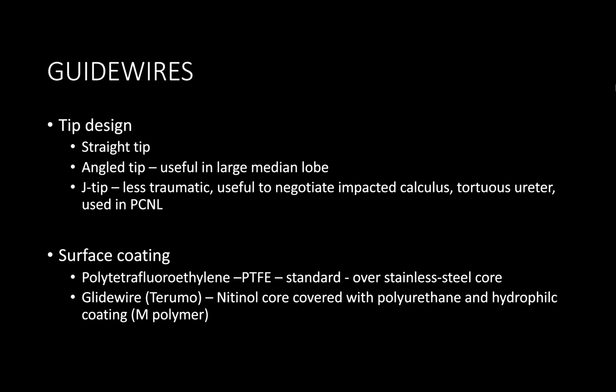Okay, you explained some guide wires. Could you further explain what is the sensor guide wire made of? So a sensor guide wire, for the majority of its length, has an inner stainless steel core, which is coated by polytetrafluoroethylene or PTFE. However, the tip of the wire is flexible and hydrophilic. This instead consists of a nitinol stainless steel core, which is coated by hydrophilic copolymer, and this contains tungsten to allow fluoroscopic vision. Any differences in the tip design?